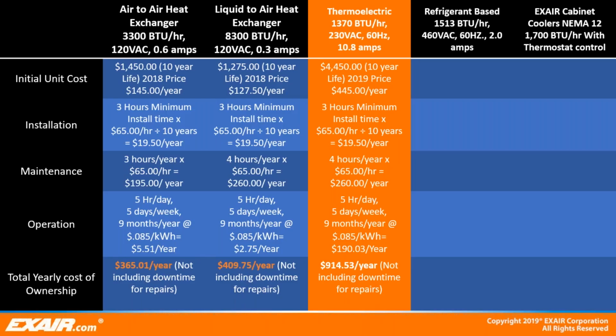The upfront purchase price of this thermoelectric cooler is $4,450. Spreading that over the expected service lifetime of 10 years, we come up with $445 a year. Using 3 hours as the minimum to install, service rate is $65 an hour, and spreading that over the manufacturer's expected service life of 10 years, we come up with $19.50 per year. Using 4 hours as the minimum for yearly maintenance and a service rate of $65 an hour, we have a yearly cost of $260.